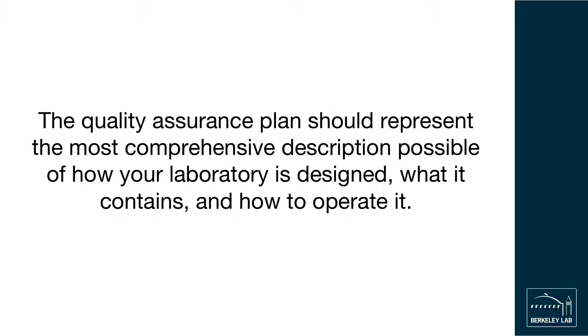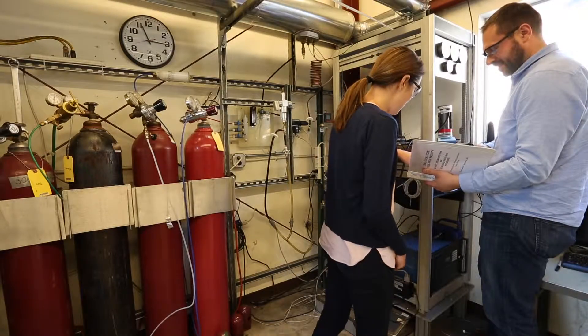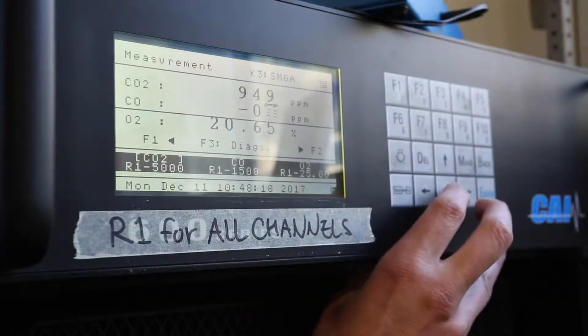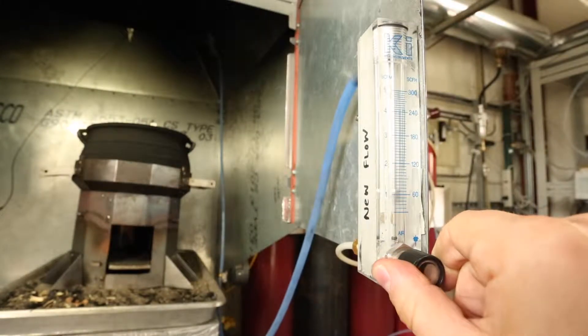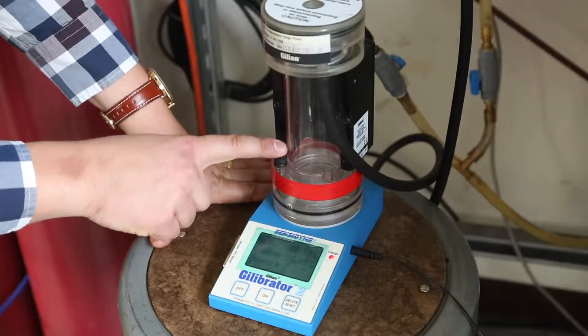While the quality assurance plan is useful as a master document for describing a testing laboratory, it is not typically referenced on a day-to-day basis. For common day-to-day tasks, we recommend writing a standard operating procedure. Standard operating procedures provide explicit step-by-step instructions on how to perform common tasks within the laboratory. For example, our laboratory has standard operating procedures for preparing and calibrating equipment before an experiment, zeroing and spanning the gas analyzer, validating duct and sample flow rates, conducting a standard water boiling test, validating collected data during the experiment, and shutting down equipment after experiments are complete.